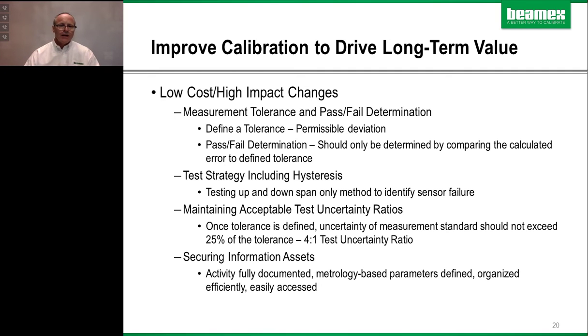So the test strategy is up the scale and back down to identify hysteresis. Third, maintaining acceptable test uncertainty ratios. Ned discussed test uncertainty ratios. That's why we have to define a tolerance in order to understand the test uncertainty ratio. Every measurement is just a snapshot in time. It's an experiment, so every measurement can be different. A test uncertainty ratio gives us a window of whether it's within tolerance or not.